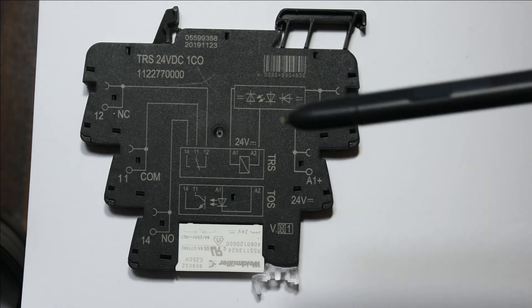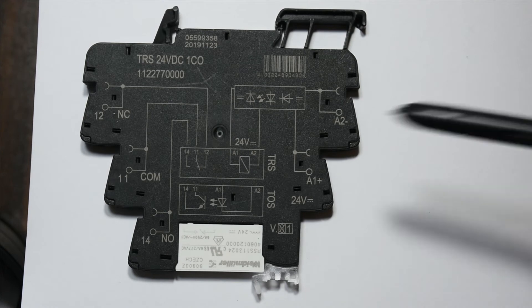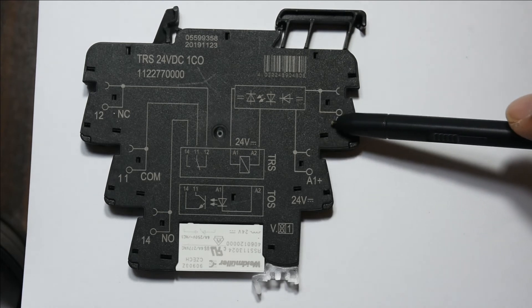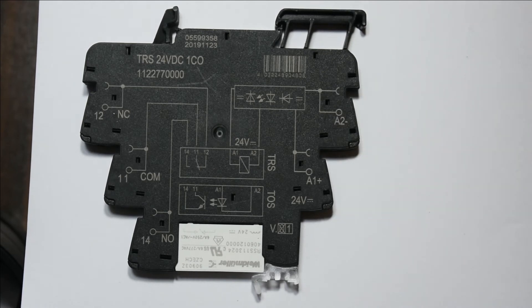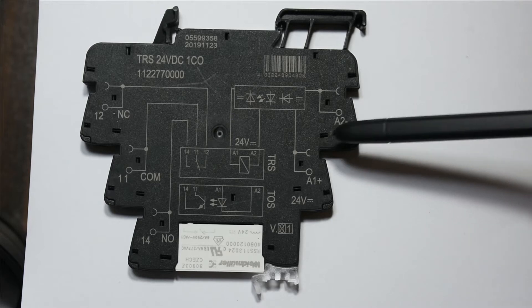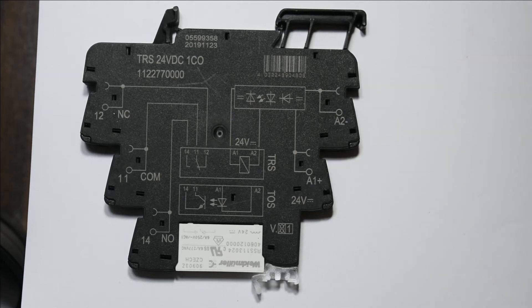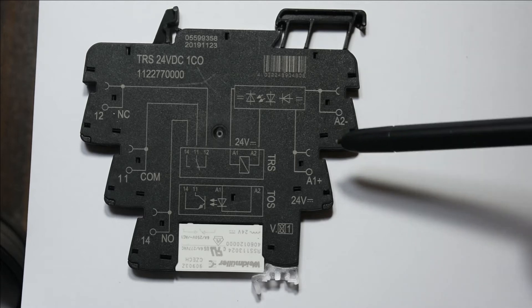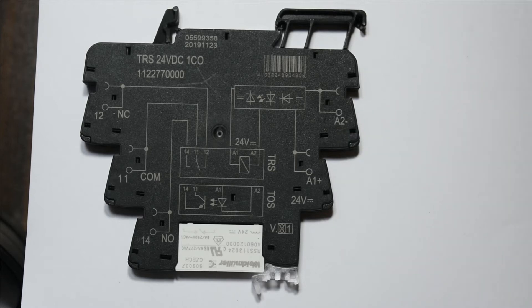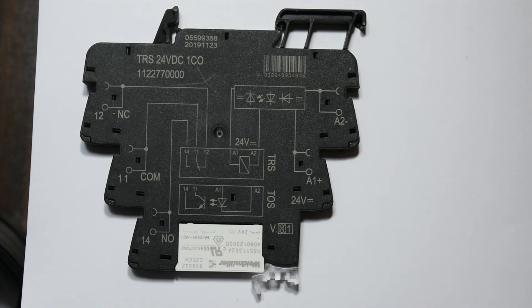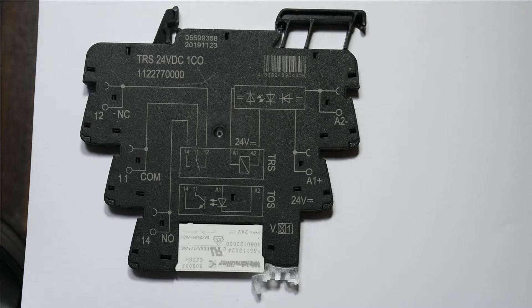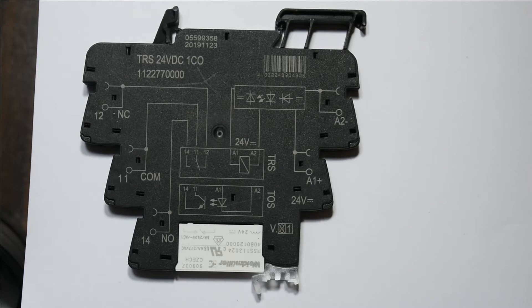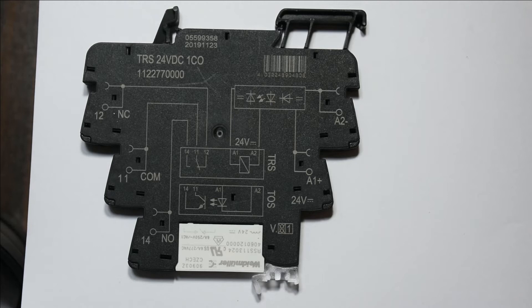When we have a PLC which doesn't have relays, we use this type. But in most cases I prefer to use this relay even if the PLC has relays. Why? Because if we have a problem on the motor, the 230 volt will burn out the relay.